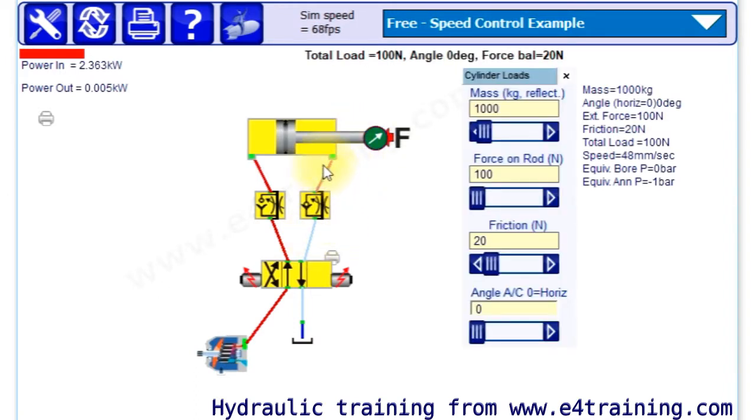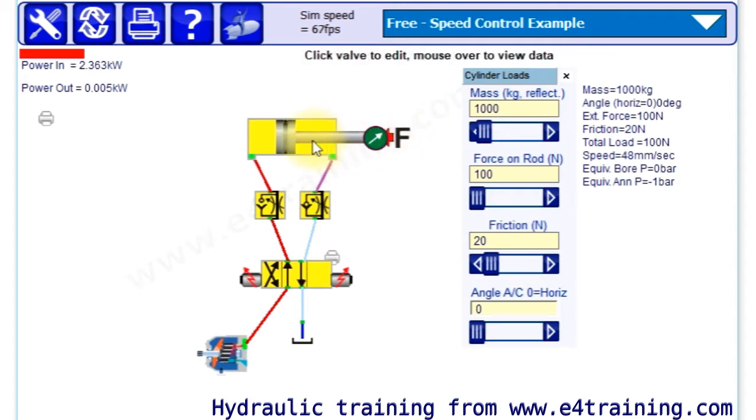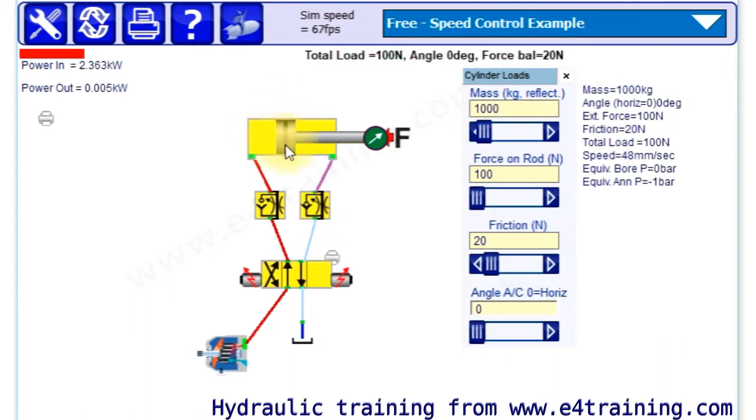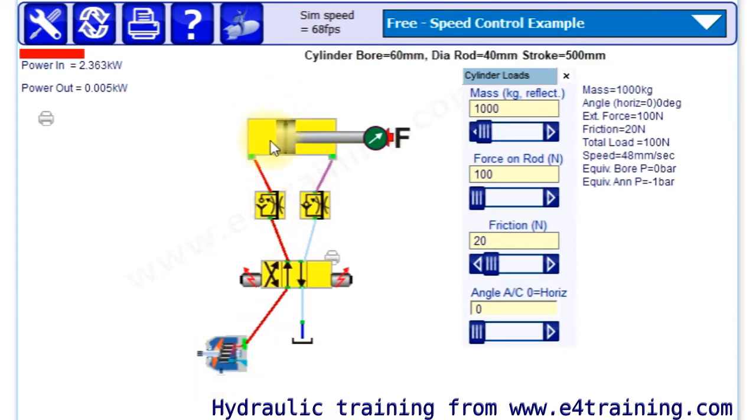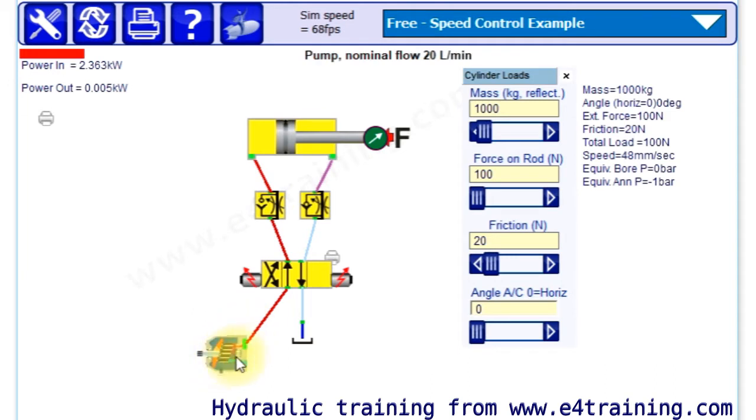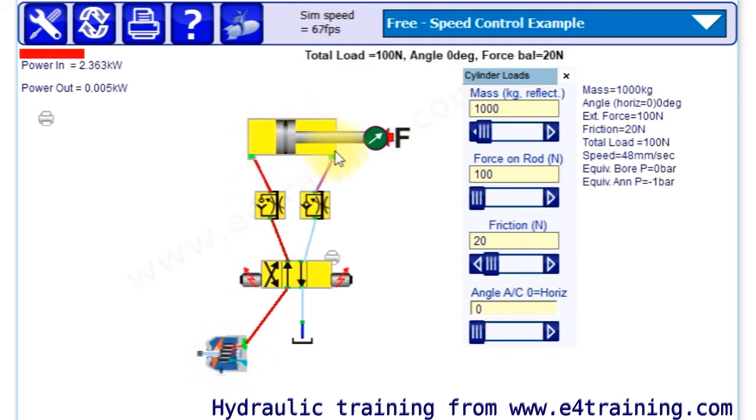If we change the load pressure, if we increase our pressure on this rod, that changes the pressure. It doesn't change the pressure there because we've got a pressure compensated pump that keeps its pressure, but it changes the pressure on this side.